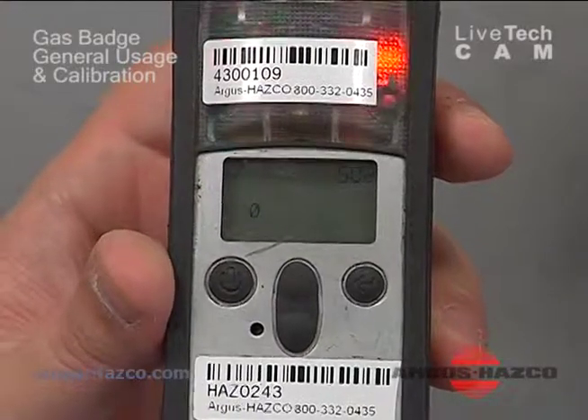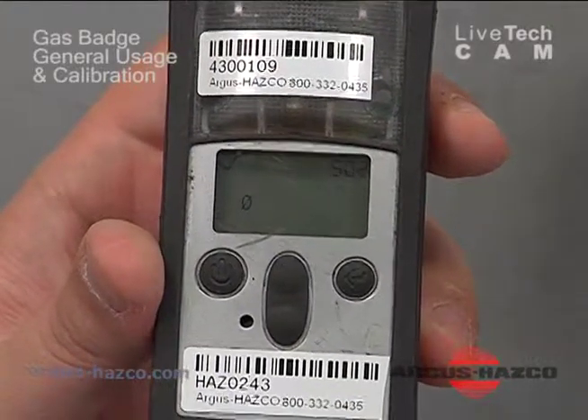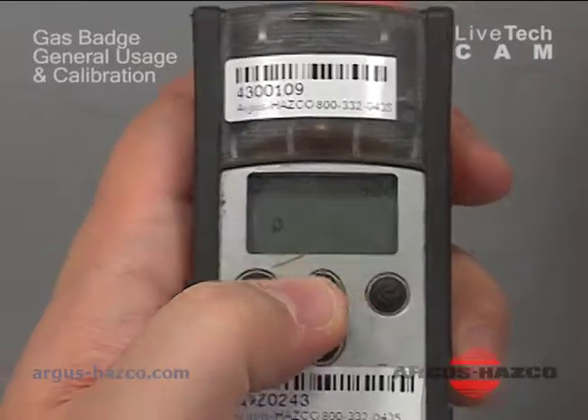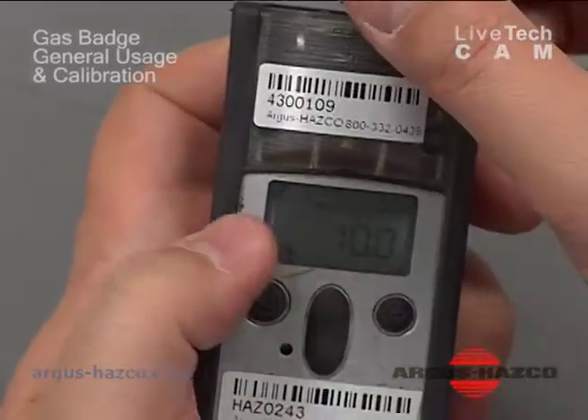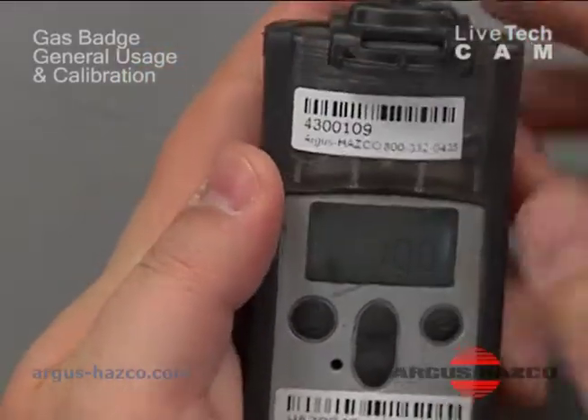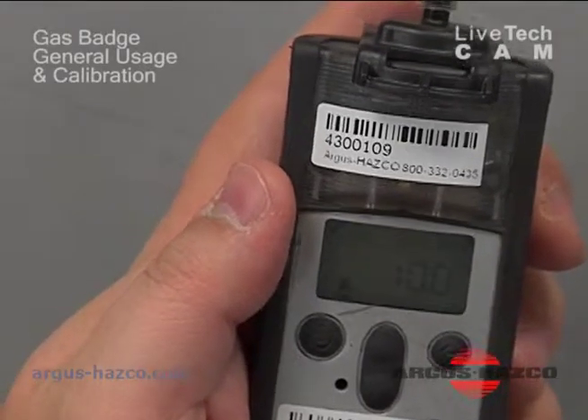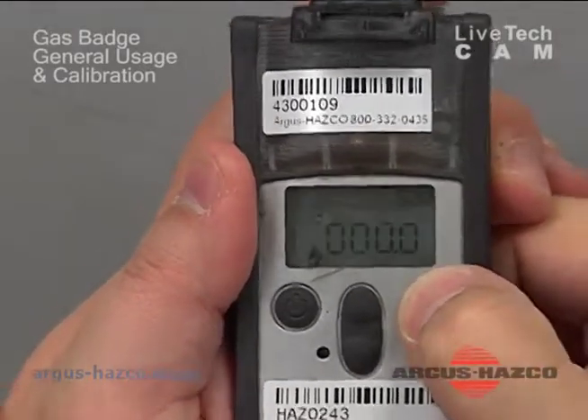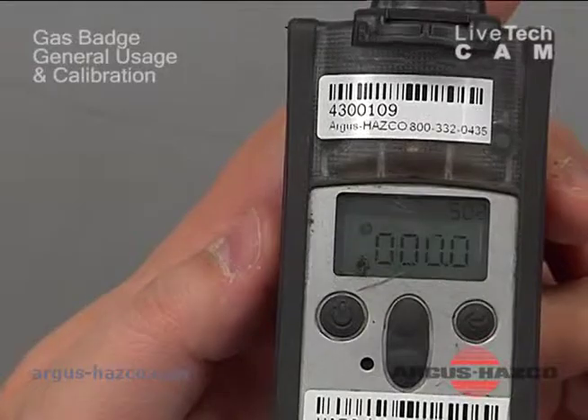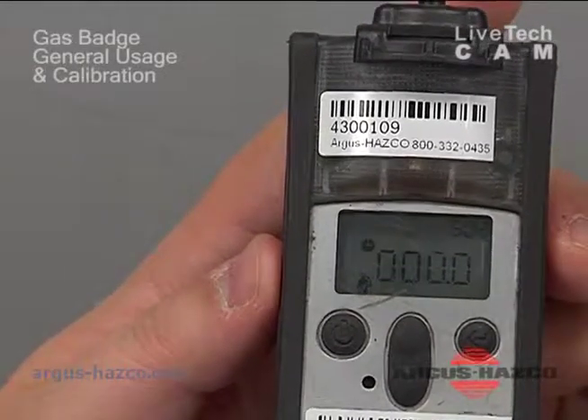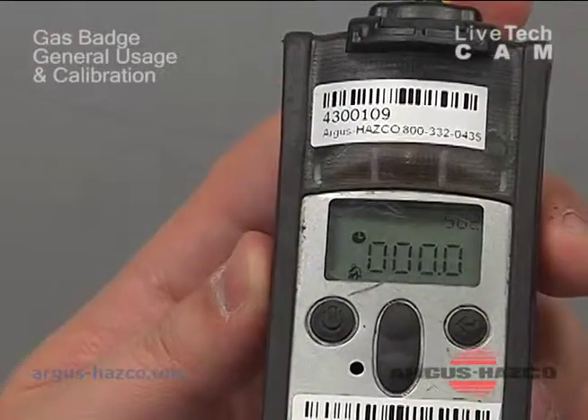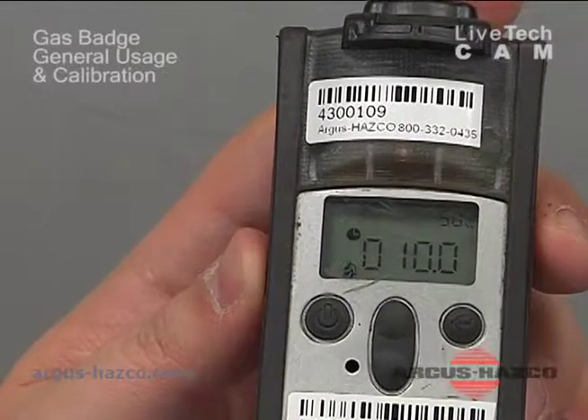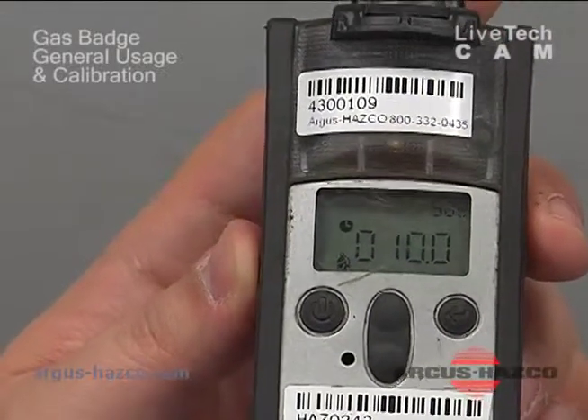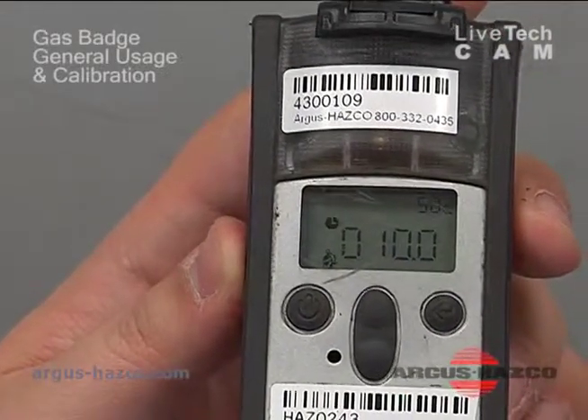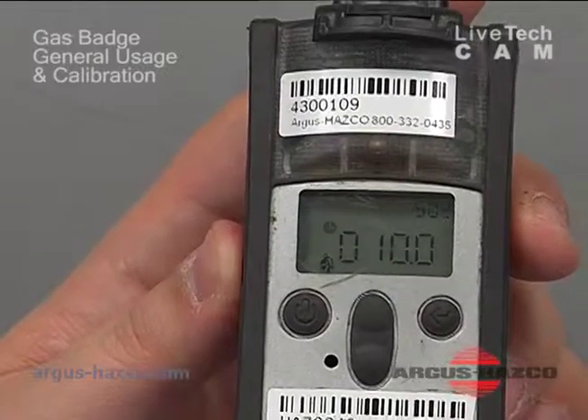Just waiting for it to 0. Okay, the 0 is passed. Now I hit up again. And it's asking you for the cal gas. So I'm going to turn the cylinder of gas on, hit the enter button. We're waiting for it to stabilize and recognize it and adjust to 10 ppm.